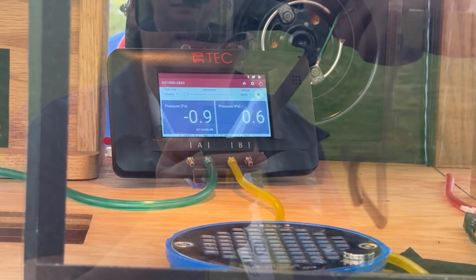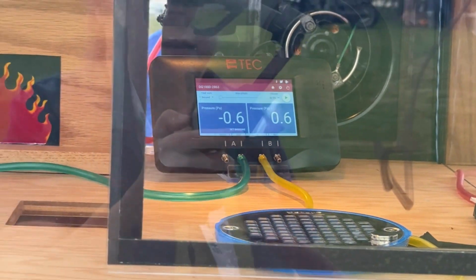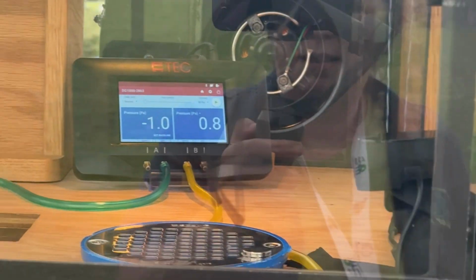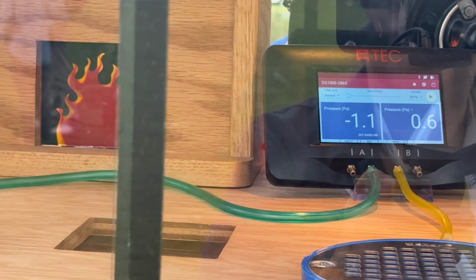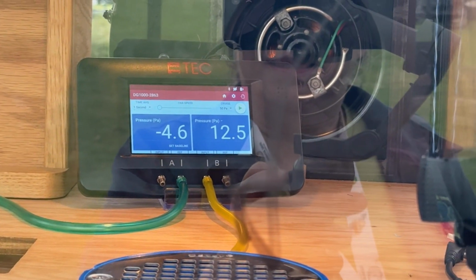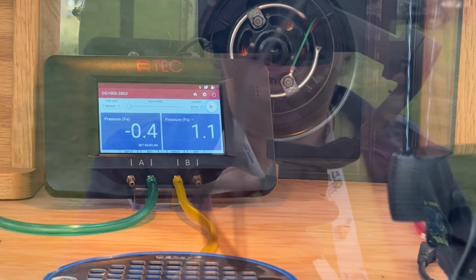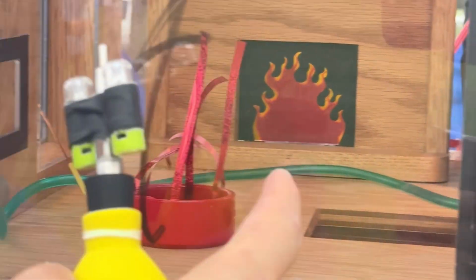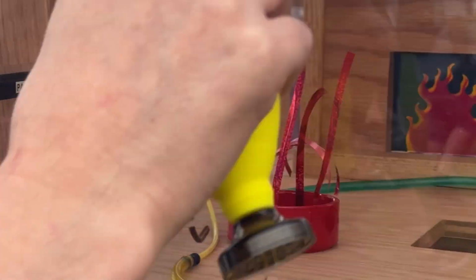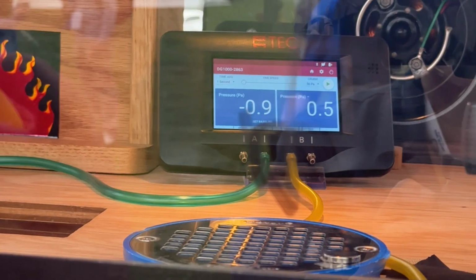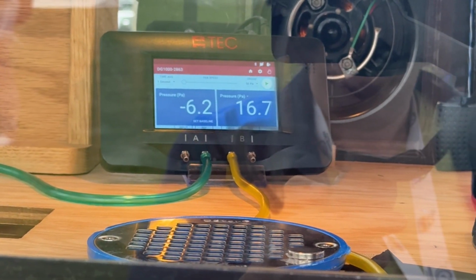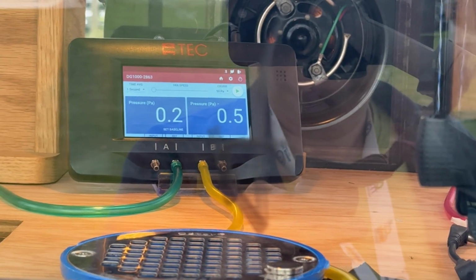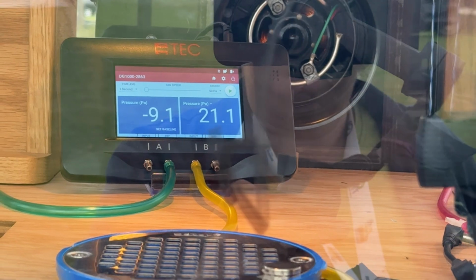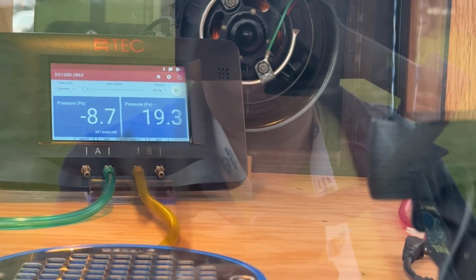Now I'm going to go over to the other bedroom door, right over here. This is the one I'm moving. I'm going to close the door, and watch not only the one with the green hose—that's the pressure in this space—but also the one with the yellow hose, which goes into that bedroom. This would be like putting a hose under the door. I'm going to close it—look what happens. So the pressure on the green side, that's this space, is actually pulling air in through the leaks.